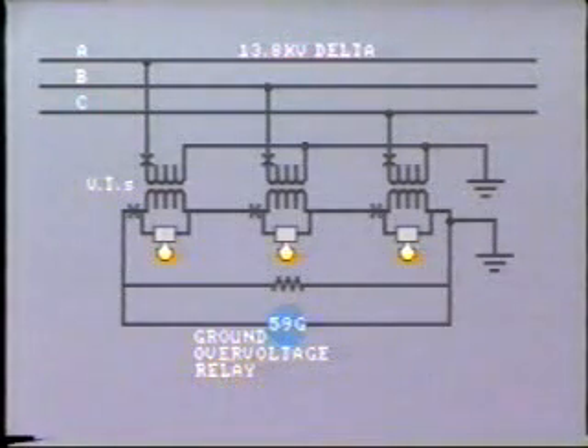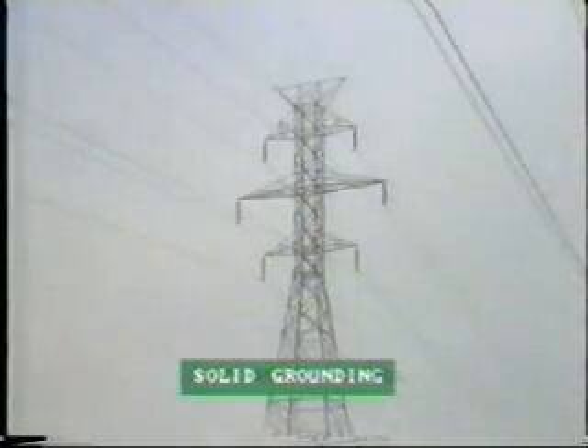Additionally, indicating lamps can be placed across each secondary, thereby giving indication of which particular phase is grounded. Now, at this point, let's briefly summarize the methods of grounding which you will encounter. Solid grounding. This is the case with most utility systems above 40 kV.